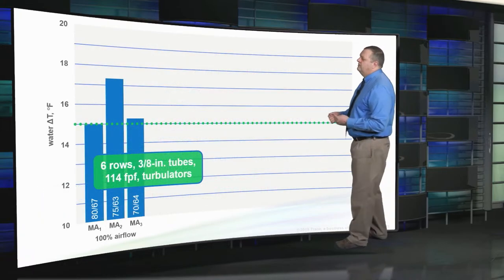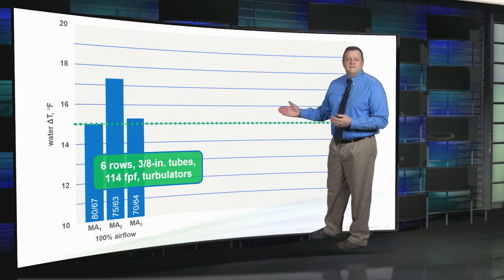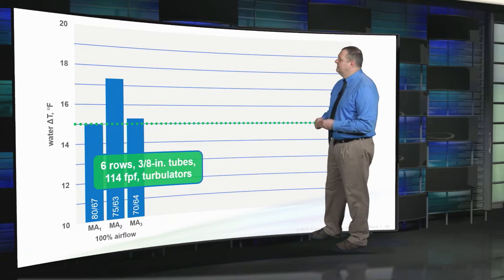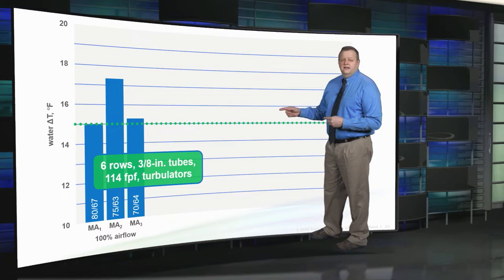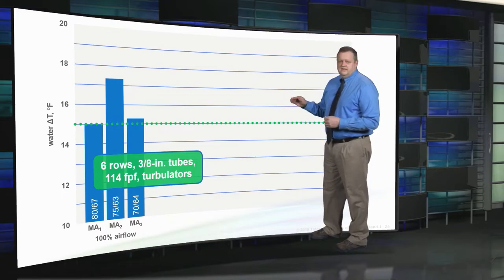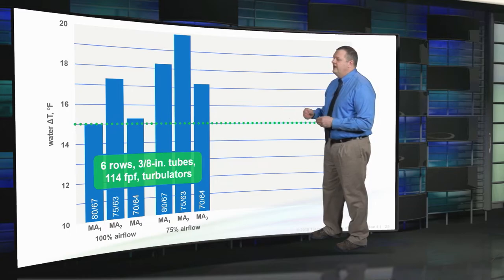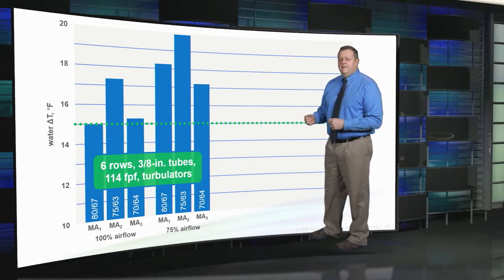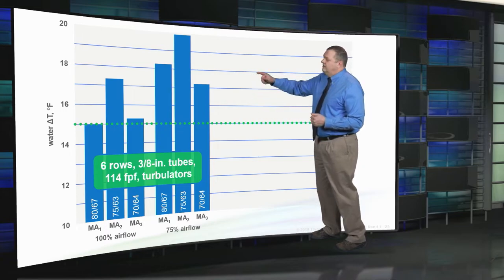To analyze how delta T is affected by part load operation, we chose two other less severe outdoor conditions when the coil will still be active, and calculated coil performance at these three mixed air conditions at two different airflows. Here's the 6-row 3/8 inch coil with turbulators. At design conditions — the leftmost column — the coil is selected to achieve 15 degree delta T. At the two part load entering air conditions, still with design airflow, the coil is able to maintain and even increase that delta T.